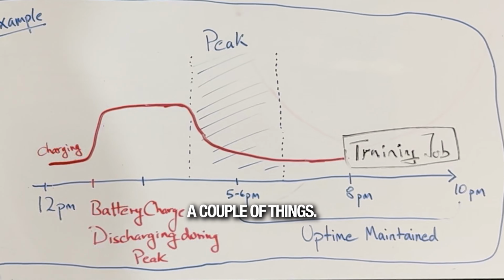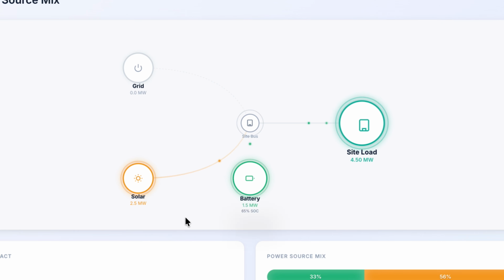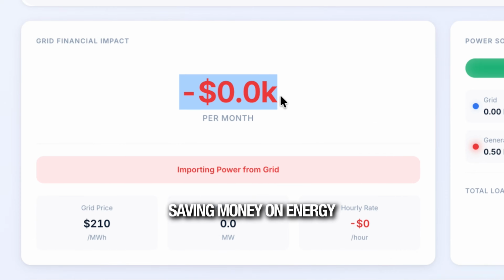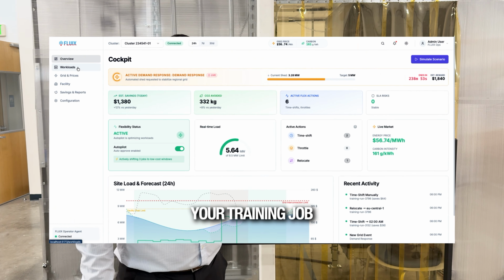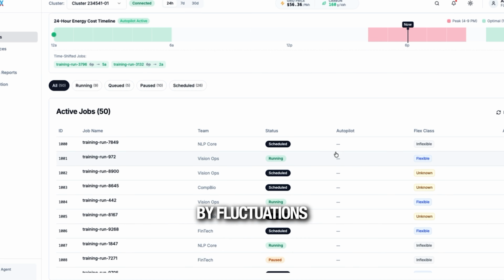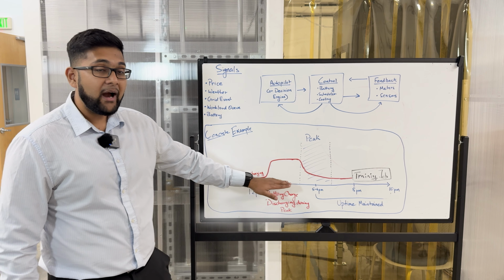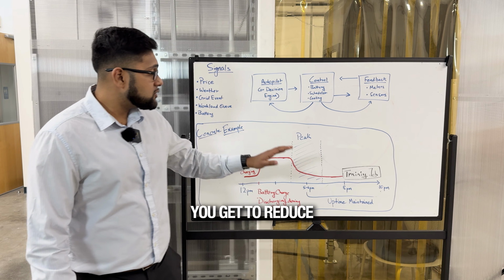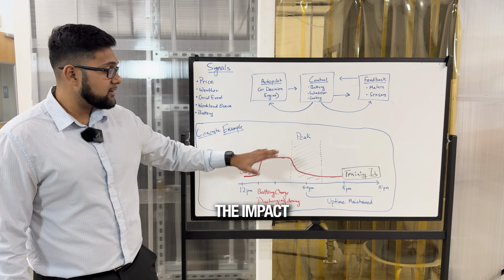This does a couple of things. One, during the peak event, you're using more on-site generation and you're saving money on energy utilization. Two, your training job is not impacted by fluctuations on the grid and switching power sources. And three, you get to reduce the impact on your facility and the grid in real time, making both systems work together.